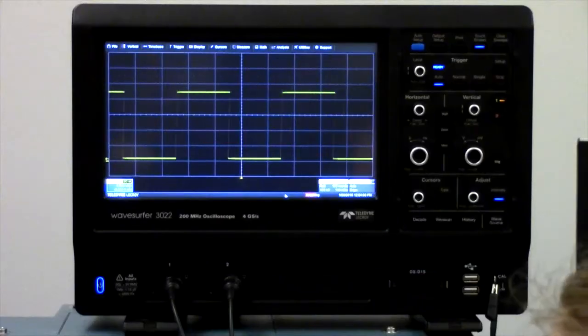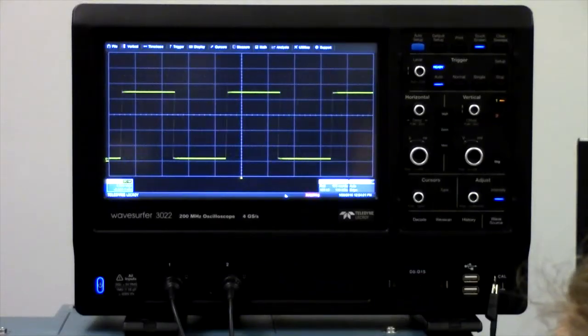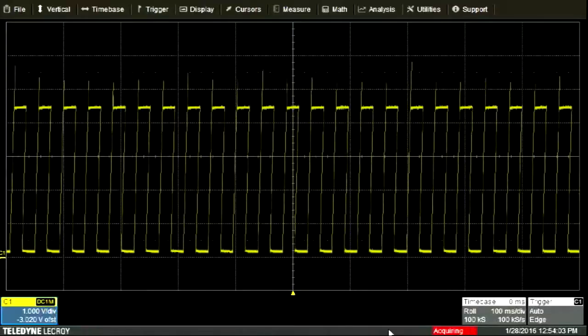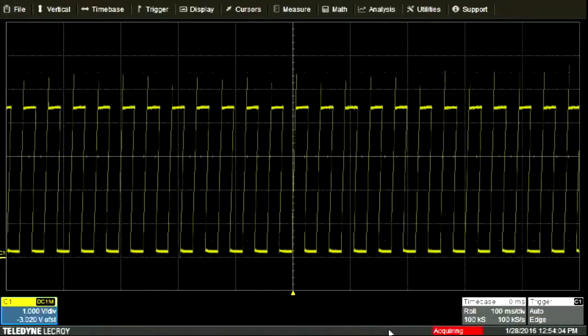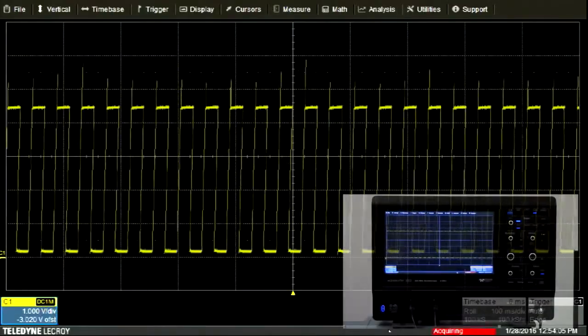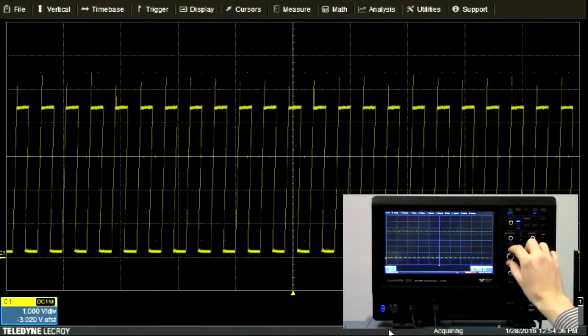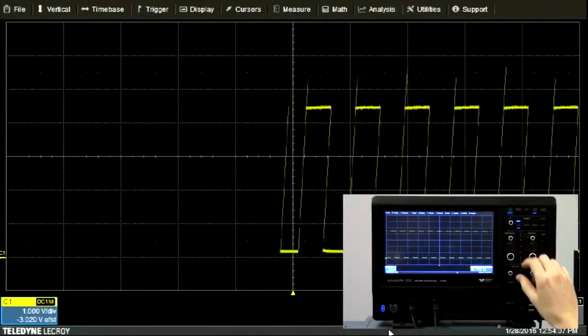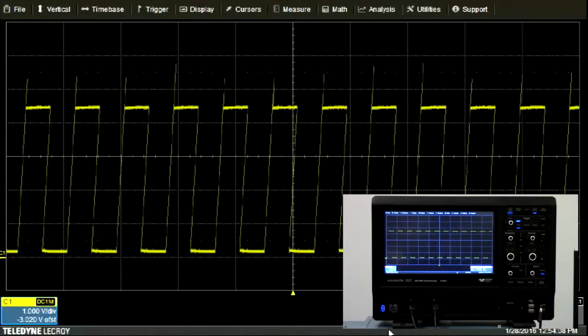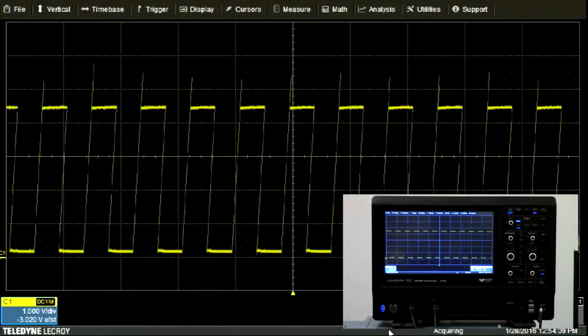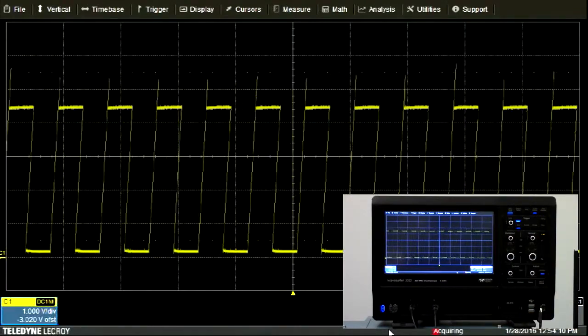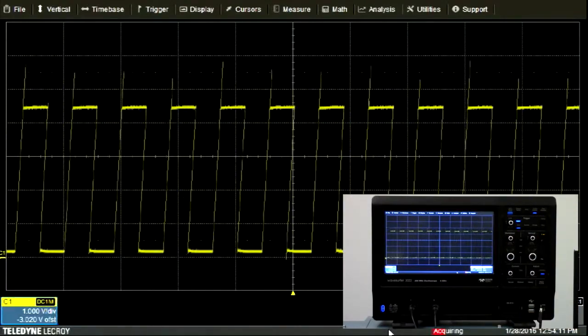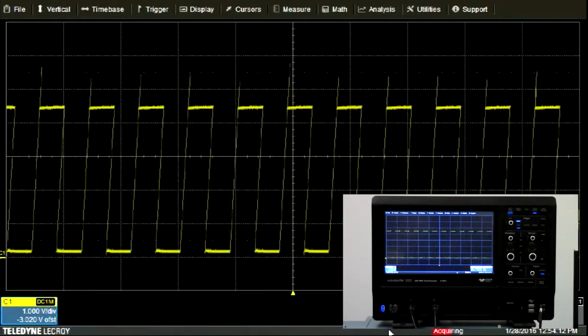As we look at faster signals, here I've increased the frequency again. We need to increase the sampling speed, but very quickly the signal starts scrolling across the screen too quickly for us to make out any features.